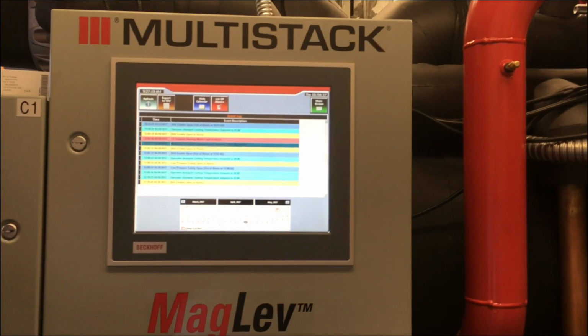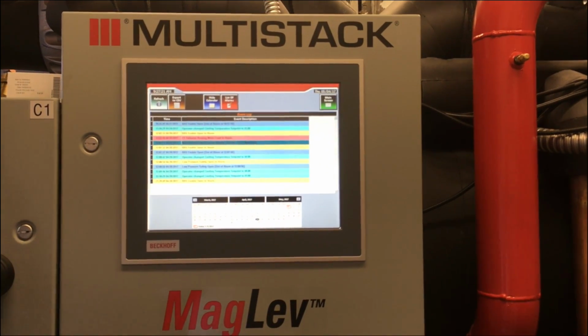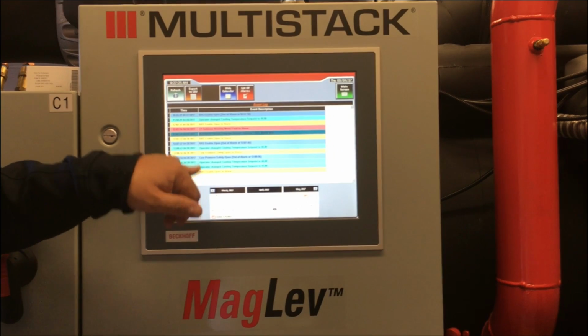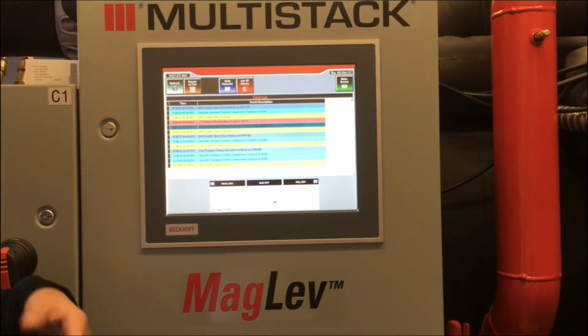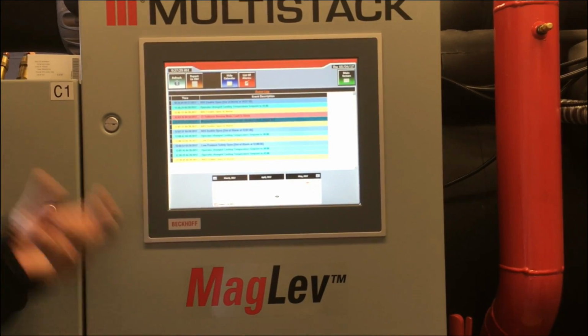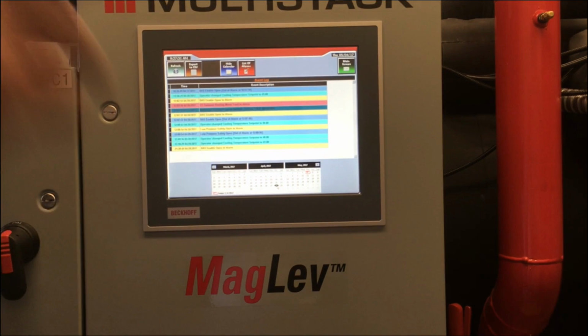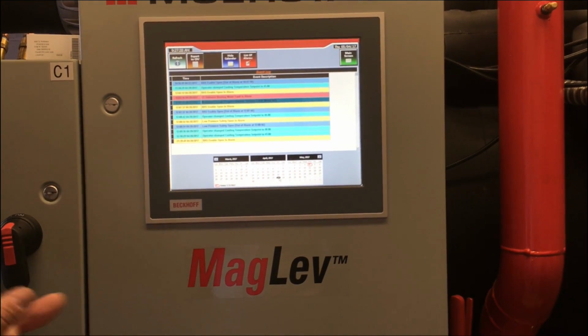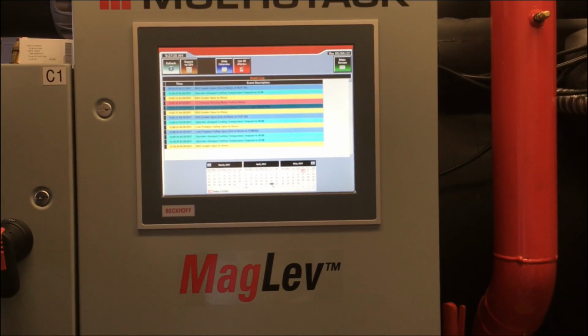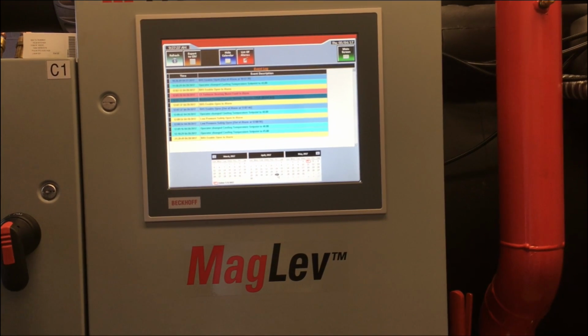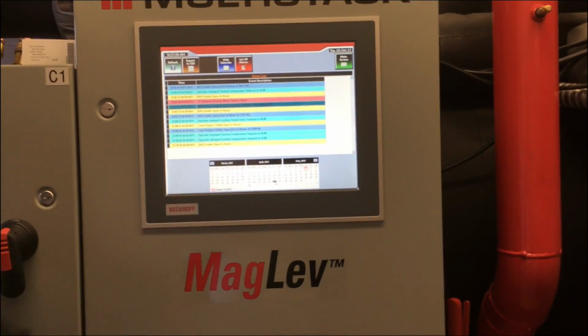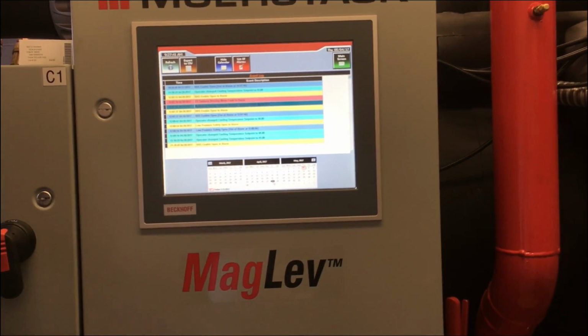But at least going through this, I can go, oh, geez, we had a power failure. Maybe that's why we had a couple low flow. You know, that low pressure safety now makes sense because it's reading 0 until it gathers data. So it grabs a low pressure alarm. As soon as it gathers the data and sees it's above 0, it comes out of low pressure. So that's why we have a low pressure alarm, and that makes sense. And then somebody tried to change temperatures, like you were saying. Yeah, we were trying to see that it is working.